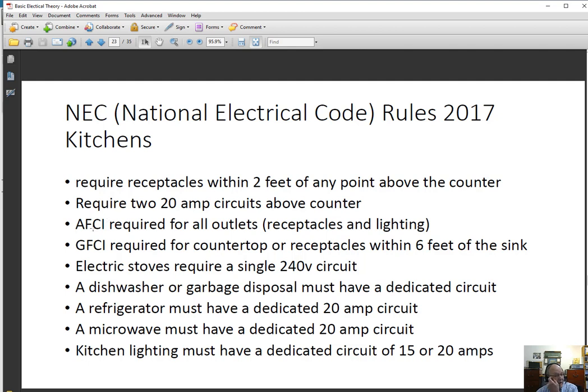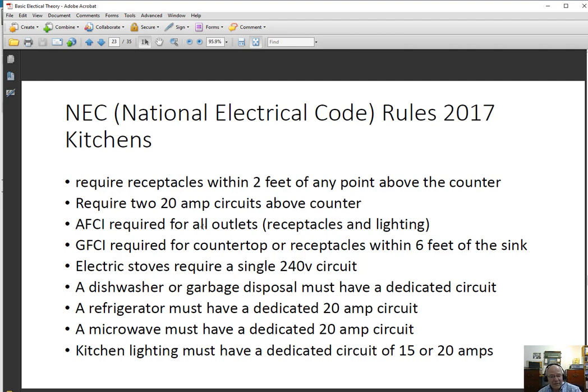An arc fault circuit interrupter is a device with a computer chip that can determine if there's any arcing going on internally to an outlet. Wires can loosen up over time — especially backwired receptacles — and if they loosen up a little you get slight arcing. Sometimes it's not enough to pop the breaker, but over time that little bit of arcing creates enough heat to eventually start a fire. That used to be required only in bedrooms so that if something was going on while you were sleeping, you'd be less likely to notice smoke. But it's now been expanded to include every outlet in the home, including the kitchen.